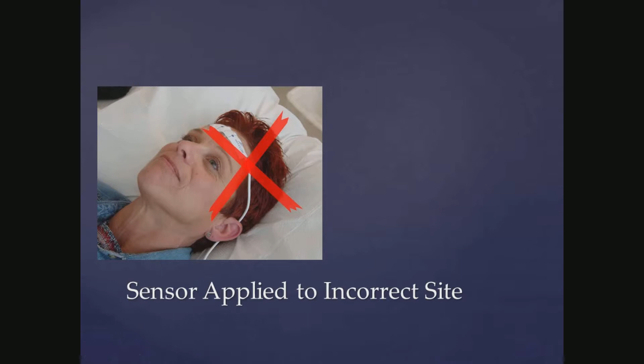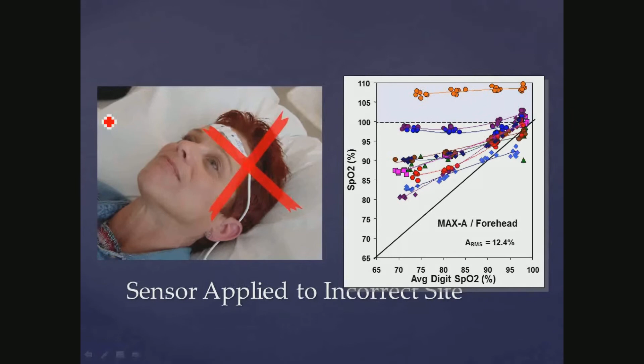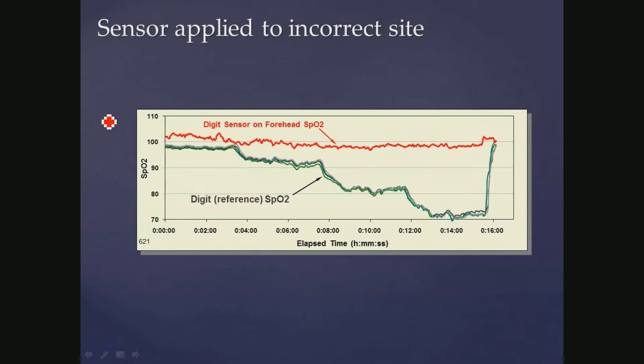Okay. I've walked into ICUs and I told nurses, you can't do that. Well, I got a number, but it's wrong, and you don't know how wrong it is. It could be a little bit wrong. It could be a whole lot wrong. I mean, if I'm doing this when the saturation is really that black line, we got some problems. Here I have my sensor designed for a digit on the forehead. Look at that sat. Here's where the reference was on the digit as this patient was desatting. And this is done in a lab. This isn't done on, obviously, we don't want our patients to probably have an 80% saturation and lower. But when they do the testing, they actually have the patient breathing 17% oxygen, and they watch them desat. How'd you like that job?